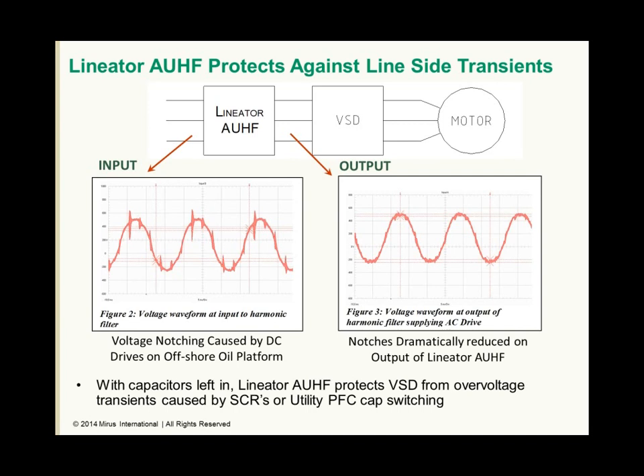And one of the things that our filter does is help protect the variable speed drive from high switching transients, such as power factor correction capacitors or utility power factor correction capacitor switching. In this particular case it was due to the notching introduced by large thyristor bridge rectifiers on an offshore oil drilling platform. What can happen is when you have these notches, you can get ringing, which can result in overshooting and additional ringing effect. So you can see that there's a high voltage peak on the input of our filter, but on the output of our filter, that ringing and overvoltage is totally removed, and the variable speed drive will see much cleaner voltage, and it does help protect the variable speed drives.